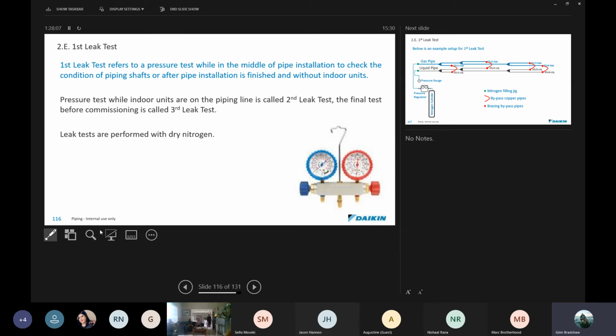So what we're trying to encourage here, and a very good way of working, is that as you're doing piping, you are crimping the piping off and pressure testing sections of piping. So you do the shafts and pressure test all the piping in a shaft. The shaft piping might run over a number of floors, so it's quite a long section of piping and can often be very difficult to get into. You pressure test that, and if you've got any problems on that piping, you'll know that you only need to look for a leak in that area.